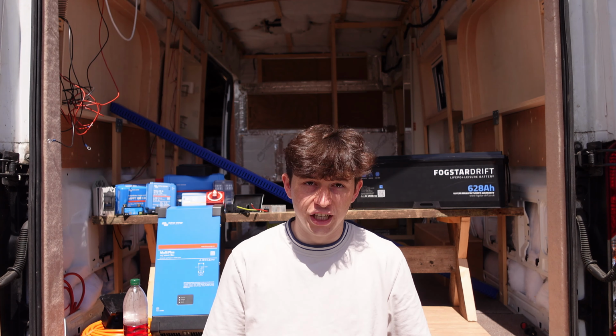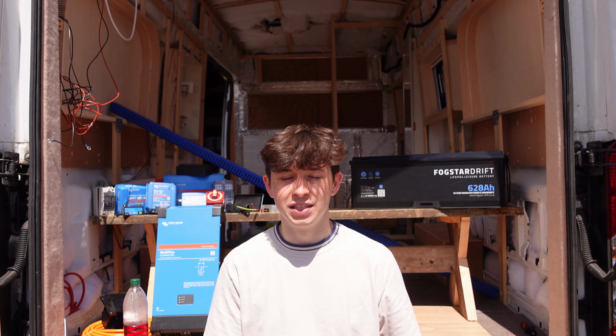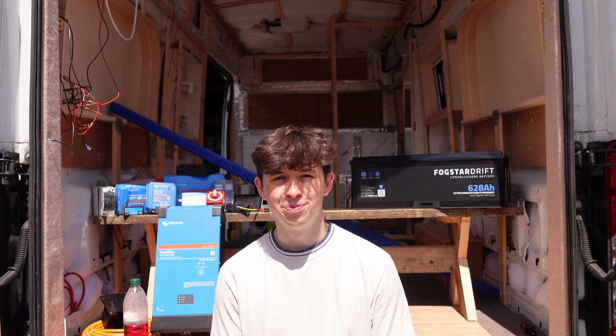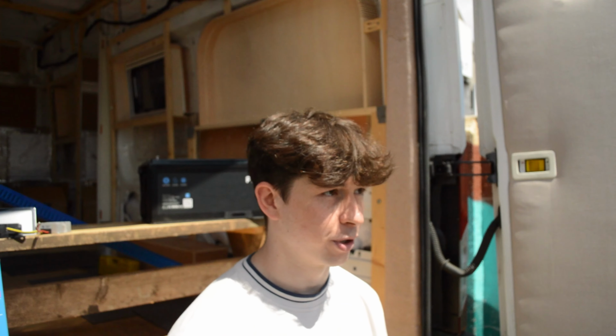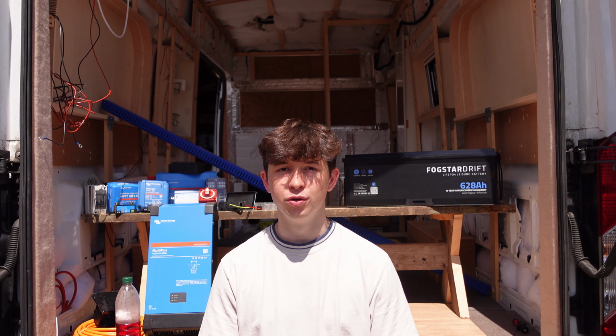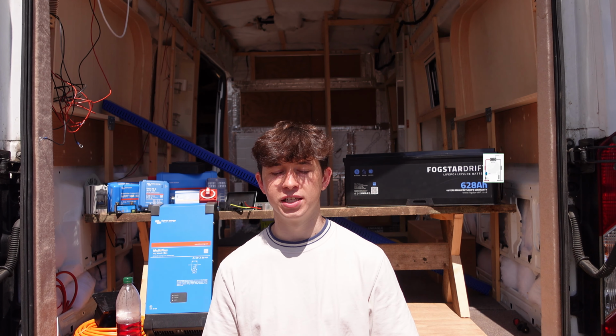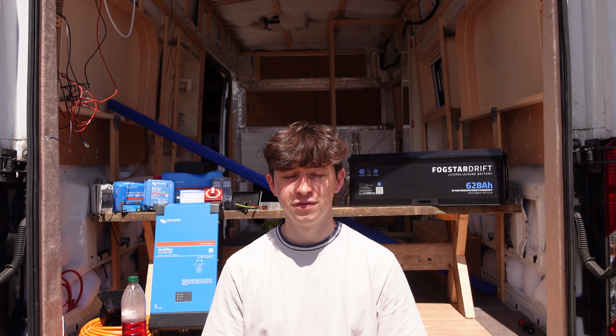In the case of an AGM battery, they also will not have a built-in battery management system, but they don't really need one. In most cases, the cost of adding this will not be worth the small benefit it gets you in terms of prolonging the life of your battery. The only thing we usually recommend adding if you are going for an AGM battery is the Victron Battery Protect. This is a little unit which can essentially disconnect your DC loads if the battery ever reaches a potentially dangerously low level.